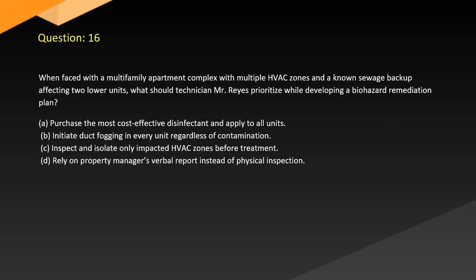Question 16. When faced with a multifamily apartment complex with multiple HVAC zones and a known sewage backup affecting 2 lower units, what should technicians prioritize while developing a biohazard remediation plan? A. Purchase the most cost-effective disinfectant and apply to all units. B. Initiate duct fogging in every unit regardless of contamination. C. Inspect and isolate only impacted HVAC zones before treatment. D. Rely on property manager's verbal report instead of physical inspection.